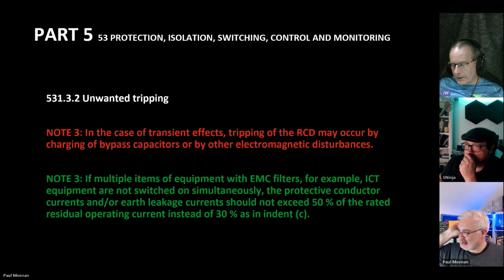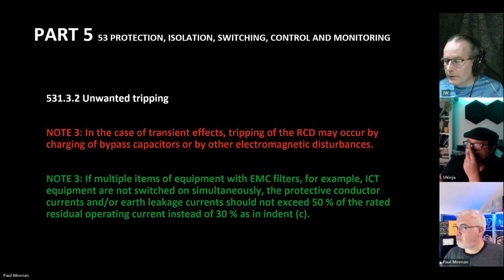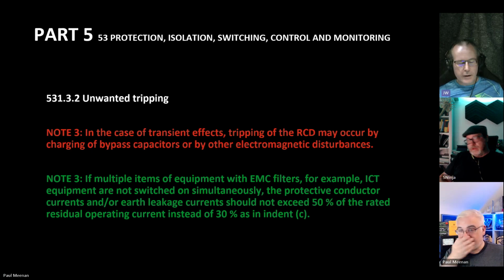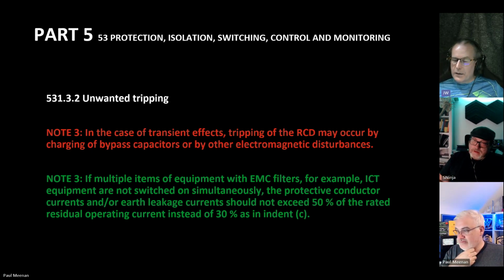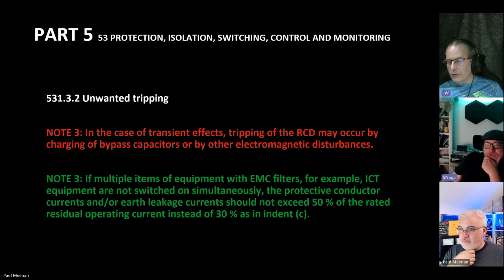That's being deleted and replaced with a new note 3, which is: if multiple items of equipment with EMC filters, for example ICT equipment, are not switched on simultaneously, the protective conductor currents and/or earth leakage currents should not exceed 50% of the rated residual operating current instead of 30%. So the only real change here is that at the moment, if you're going to put an RCD on the circuit, you're not supposed to have more than 30% of that RCD's rating as leakage. So for a 30 milliamp, it should be 9. But now, in this particular circumstance, it can go up to 50%, which is sort of pushing up against the bottom of the actual trip range, the threshold. So it would be 15 milliamps in the case of a 30 milliamp device.